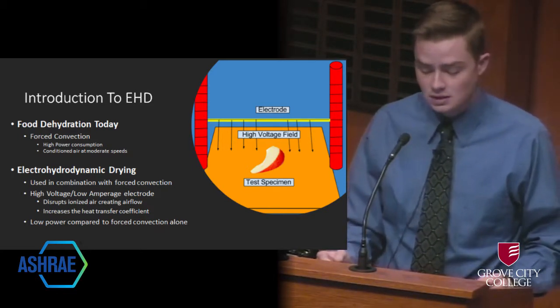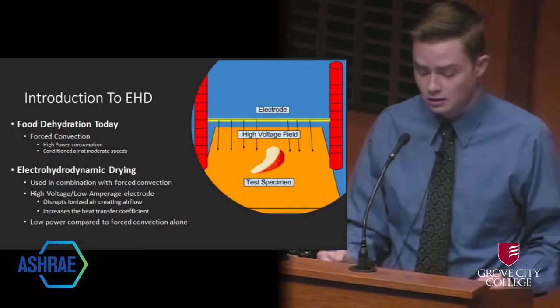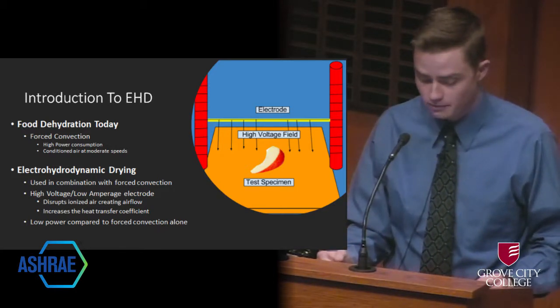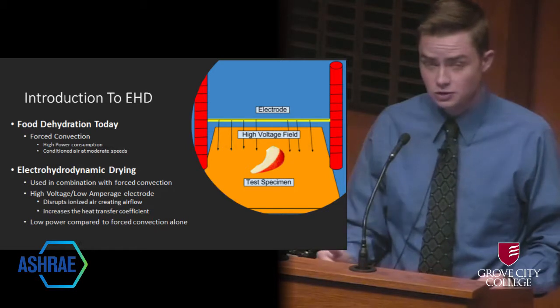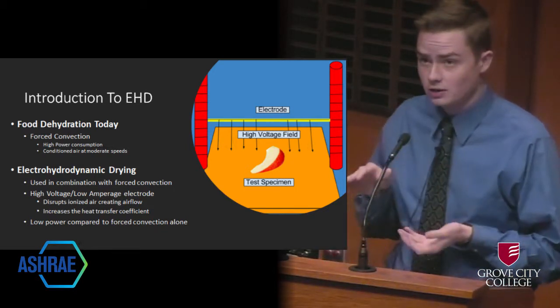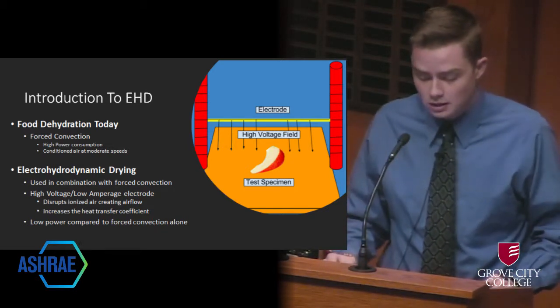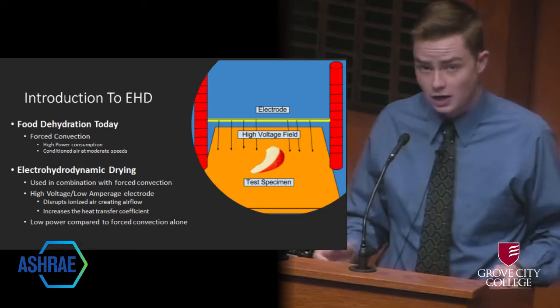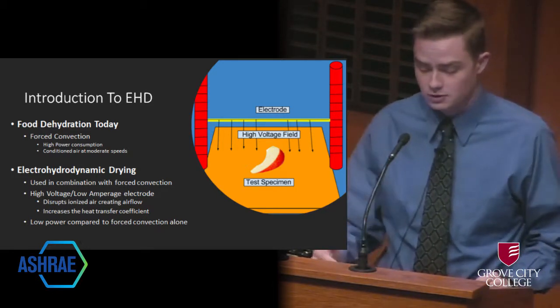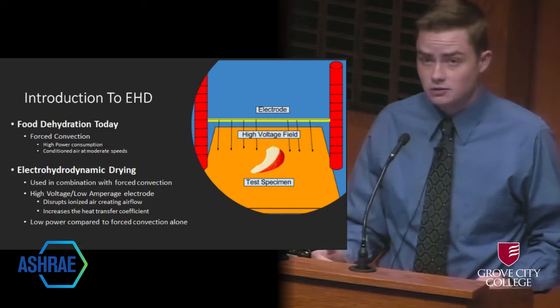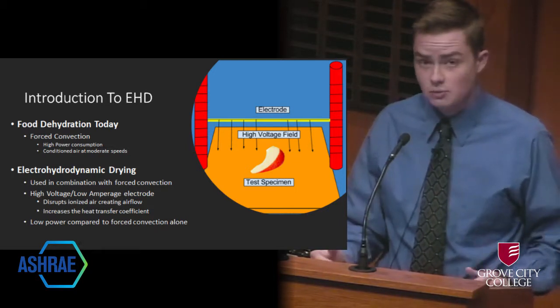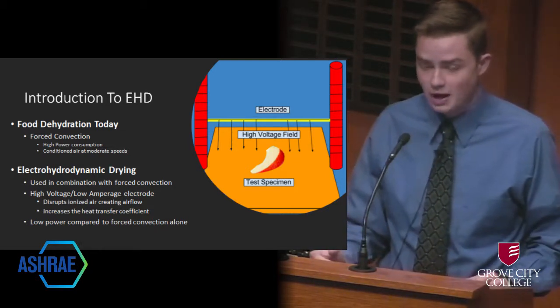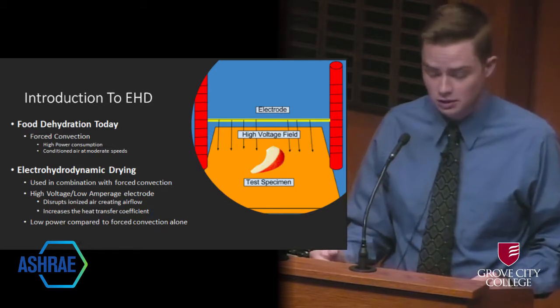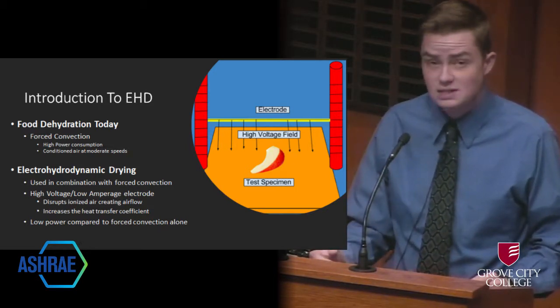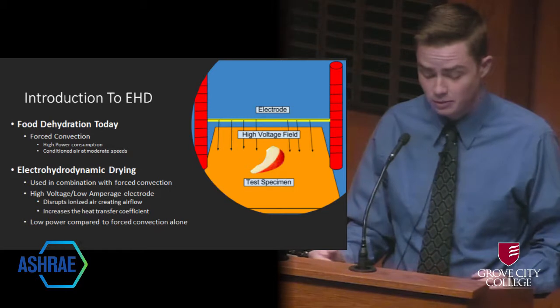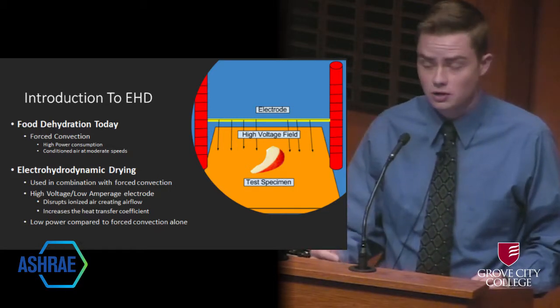One of these is electrohydrodynamic drying, or EHD for short. EHD uses an electrode suspended above a grounded conductive plate. The electrode is supplied with a voltage anywhere from 8 to 30 kilovolts. This creates an electrostatic field that disrupts the surrounding air by the passage of electrons to the grounded plate. This creates a secondary airflow in the system that increases the overall heat transfer coefficient.